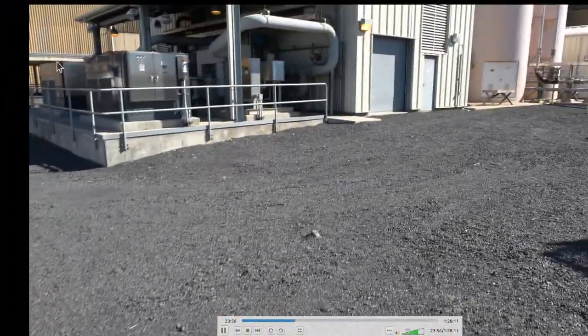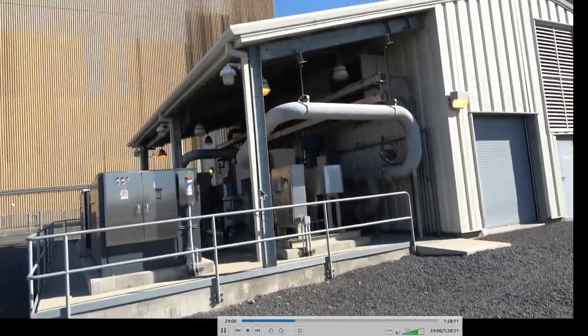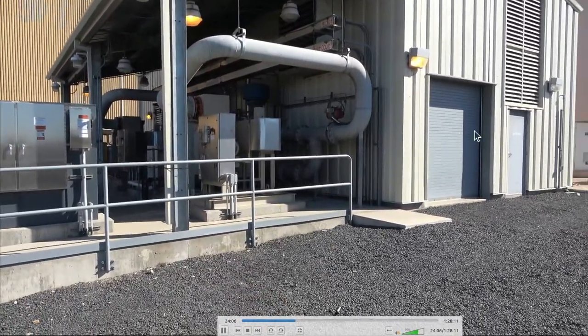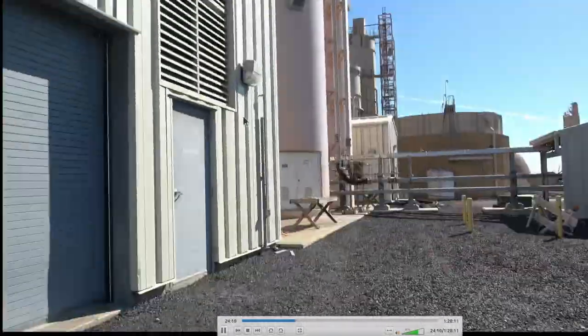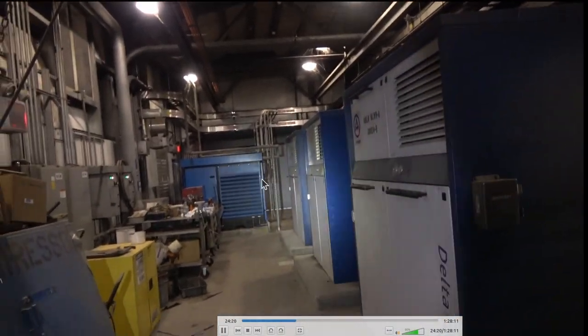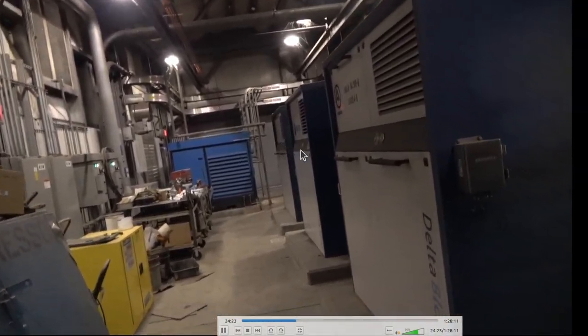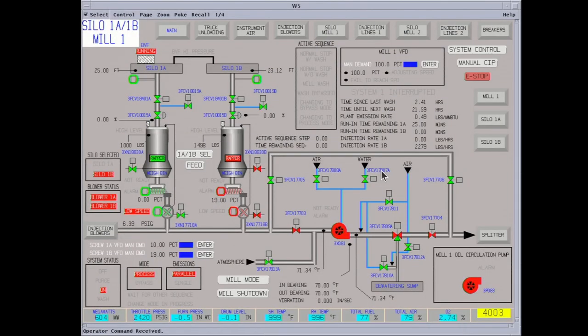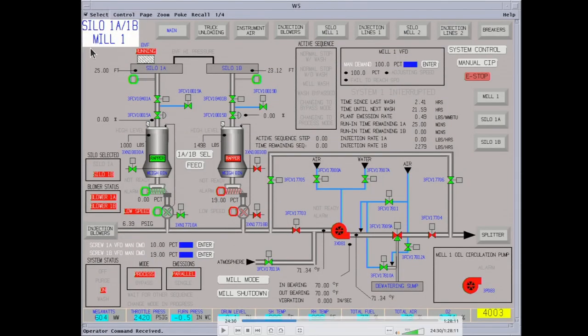The chillers feed into the blowers — there are two unloading blowers and two process blowers, plus air compressors to run the system. These are the blowers for the DSI injection system. Here's another view of the mill and silos with a screw feeder. The purpose of this system is to maintain sulfur emissions down under 0.3. This is a rotary vane feeder with an airlock — this section is under pressure at six pounds — so it keeps air from blowing back through. It has seals on the blades and it dumps the product down to be carried through the line.